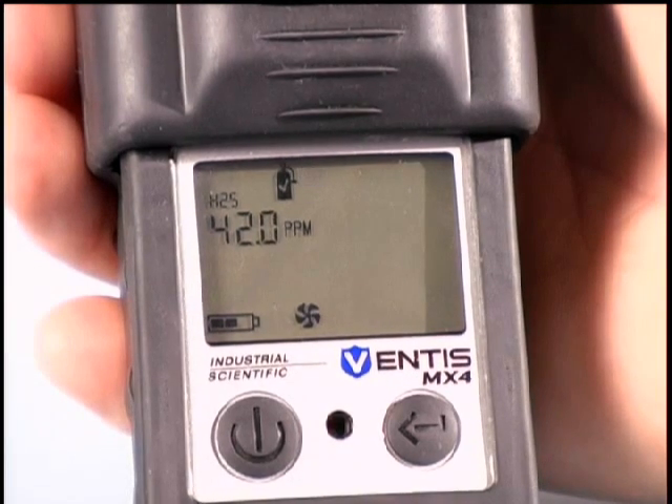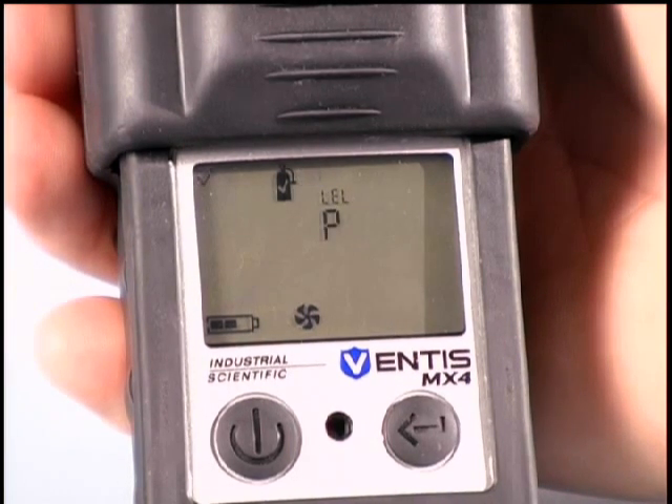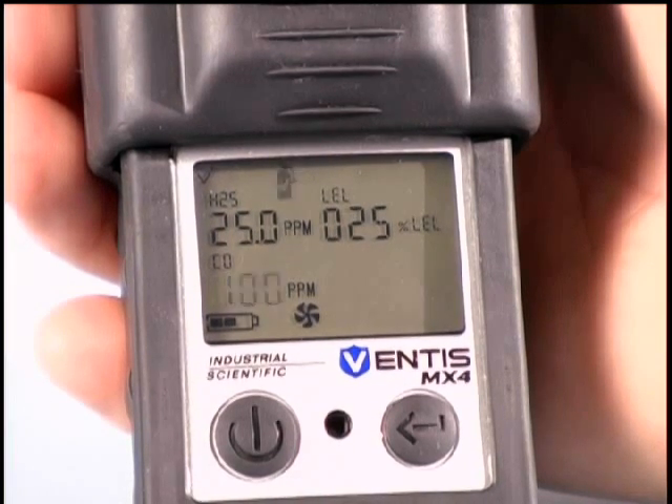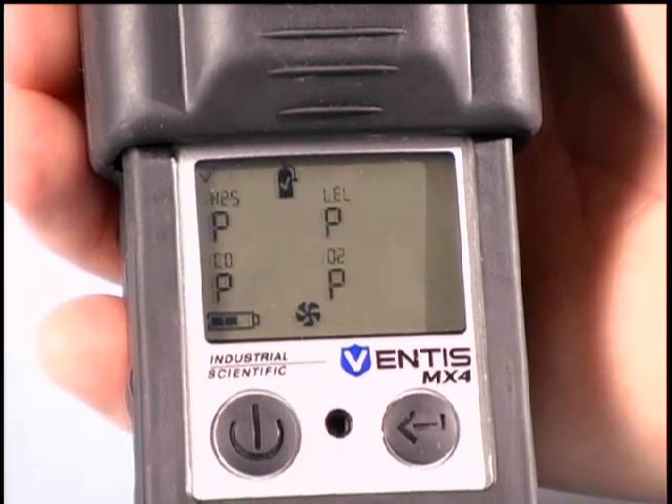The Ventis MX4 will automatically detect the gases present and begin the calibration process. This calibration process will take a few minutes. Once all the Ventis MX4 sensors are calibrated, the instrument will display P for pass or F for fail for each of its sensors. If a sensor failed its calibration, that sensor will display an F once the instrument has returned to the real-time readings screen. The instrument will beep once a second, indicating a failed calibration for that sensor.